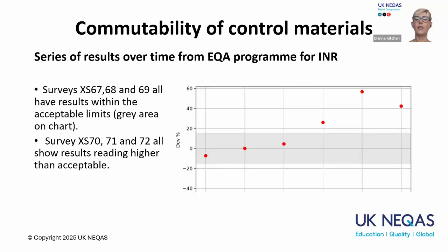You can see for the first 3 readings, they're within the acceptable. That covers about 9 months, because I said it's 3 monthly, and then the latter 3 tests are outside the range and they're all reading high. So for the latter 9 months, the EQA was reading too high and they would have failed their EQA for this. Next slide, Jen, please.